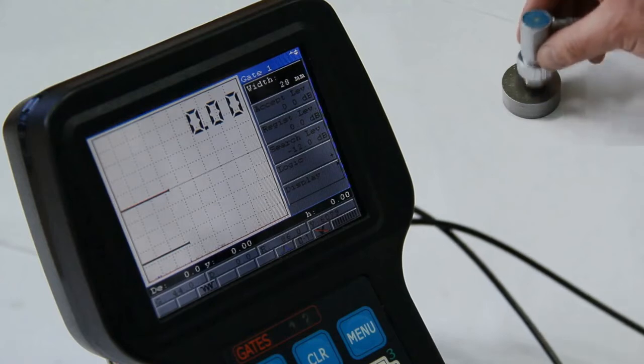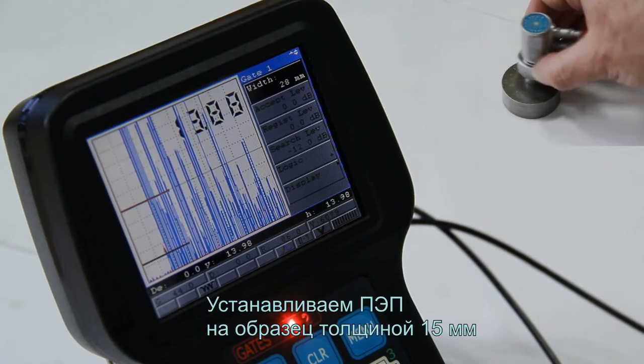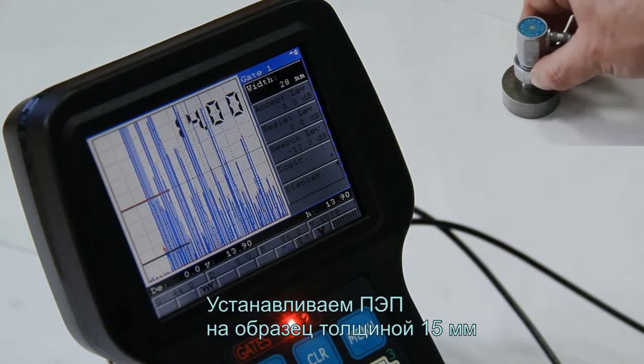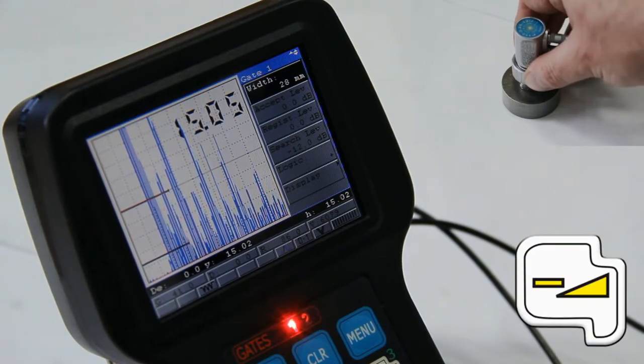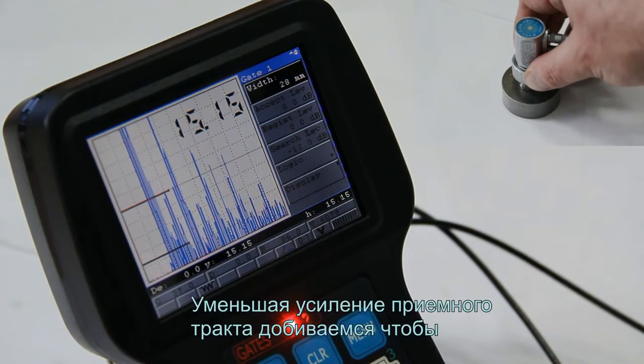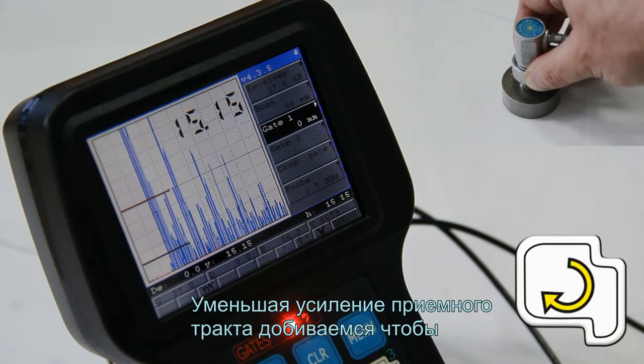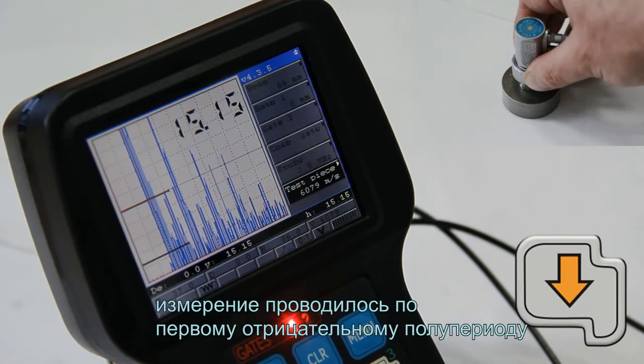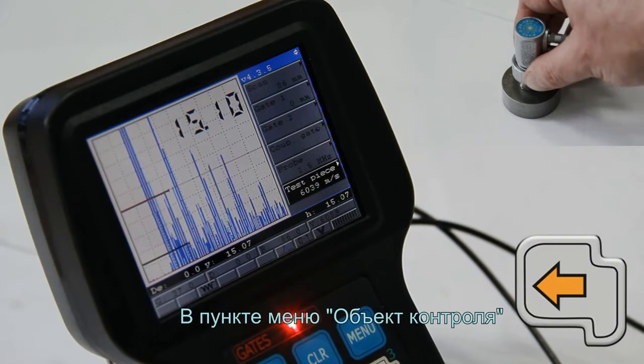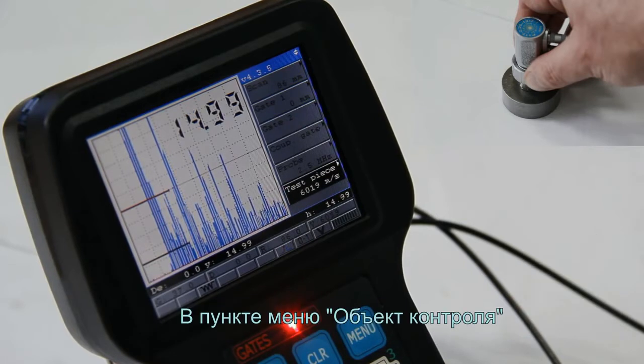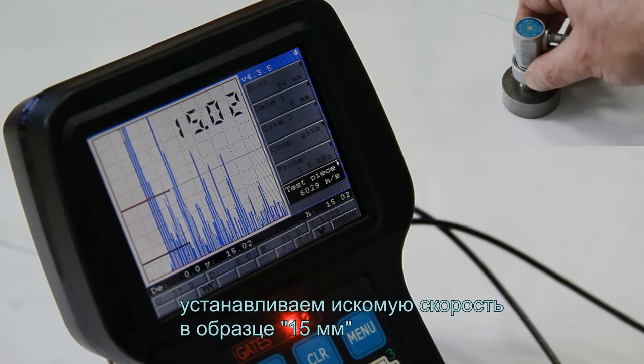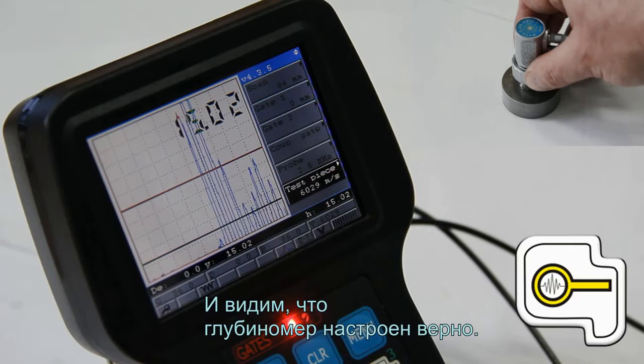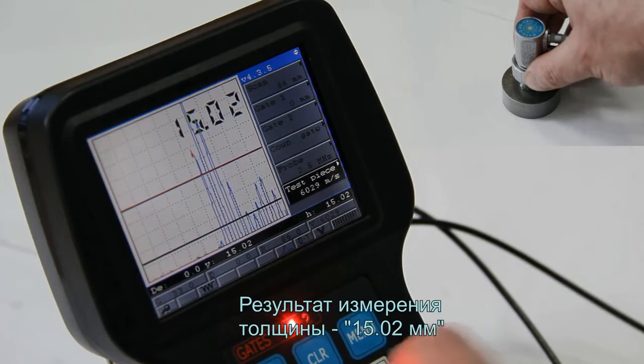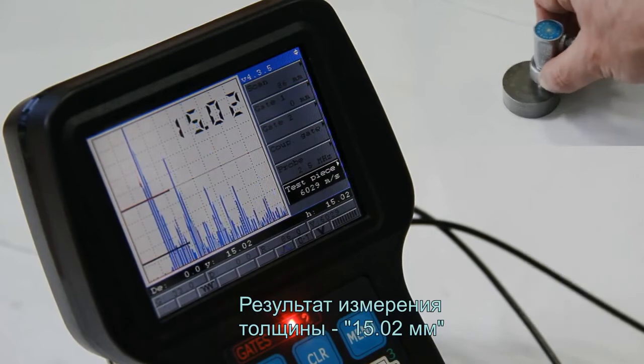Place the probe at 15 mm thickness block. When reducing the gain of a reception path, achieve the measurement to be carried out by the first negative half period. In the Test Piece menu, set up the required velocity in a block to 15 mm. Observe that the depth gauge is set up correctly. The result of thickness measurement is 15.02 mm.